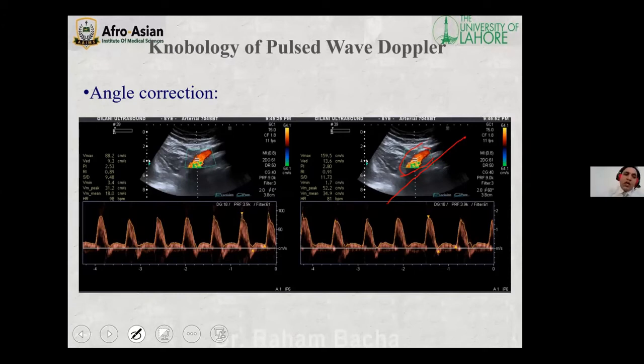And here you can see in the first image there is no angle correction. The angle correction has not been done. By default, the machine assumes that the angle is 0. At that point, the peak systolic velocity measured by the machine was 88.2 centimeter per second. And when you did the angle correction, the exact velocity in that particular vessel is 159 centimeter per second. There is a huge difference between these two velocities. So the accurate one is this one. Keep it in your mind.